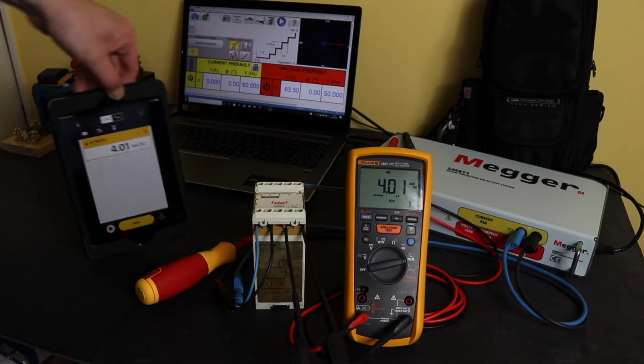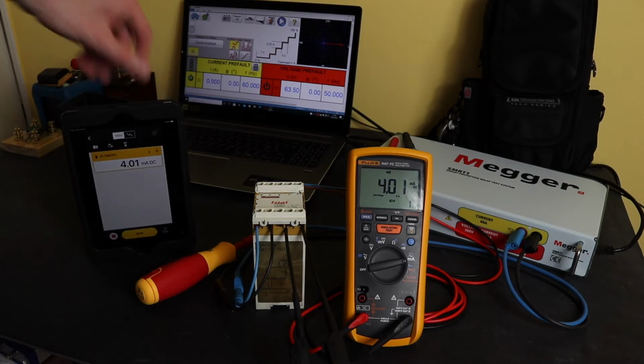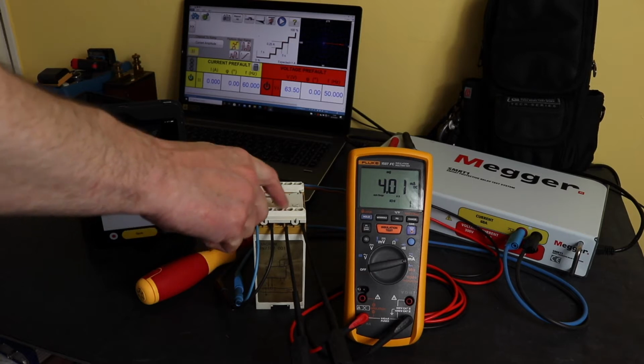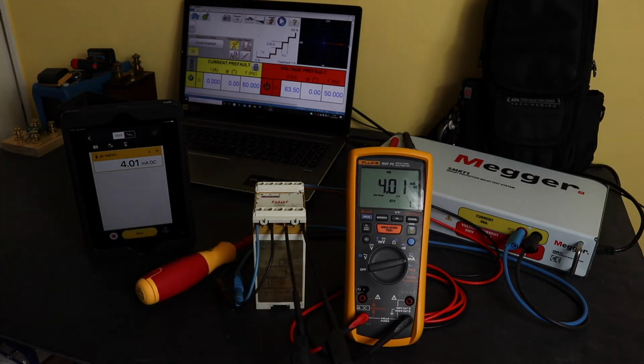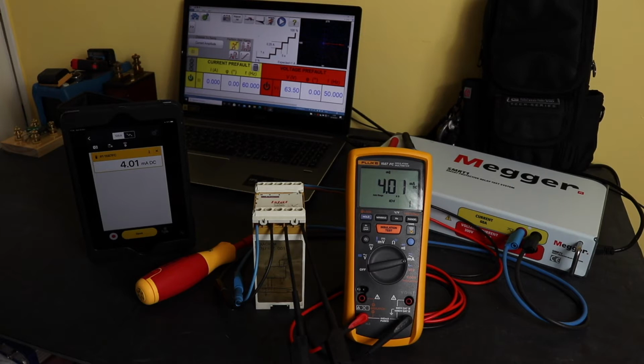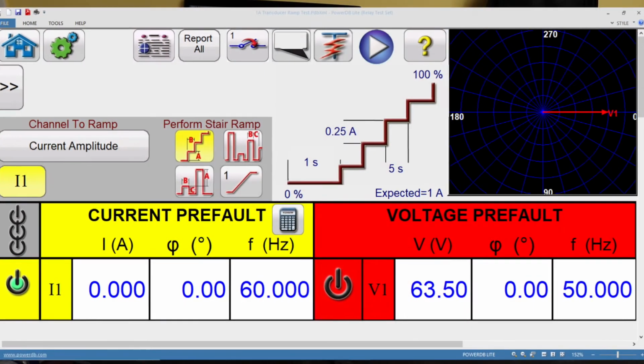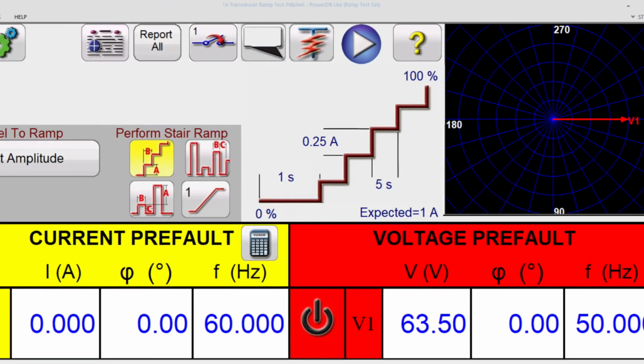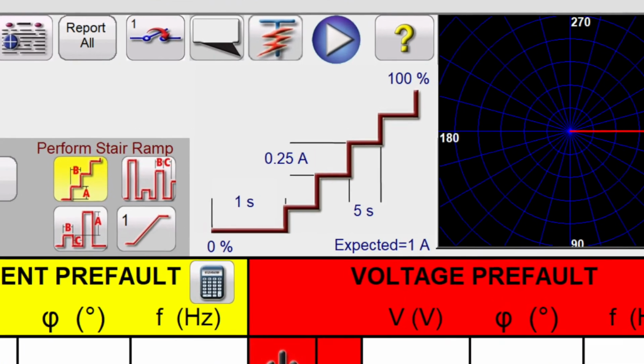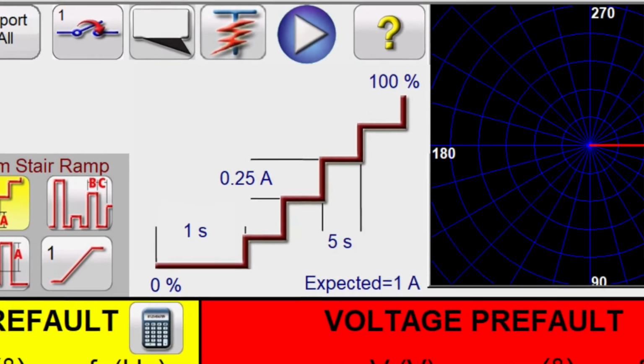One annoying thing about this is that the iPad will not record landscape, so we have to tip it up onto its side like that. The other connection I've got into the transducer is 110 volt AC, which is coming from a power supply outside of the picture. That would normally come from the panel that I'm working in. At the back I've got the laptop running, and that provides the control to the Megger SMRT1 there. I've got a ramp set up on this that is 0 to 1 amps AC, 50 Hertz, and I've got 4 steps on it at 250 milliamp steps.